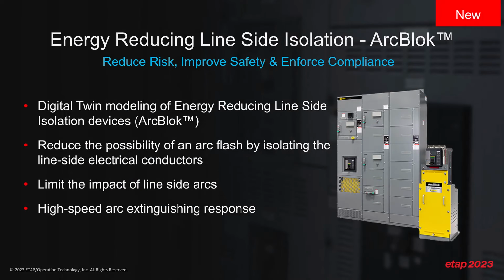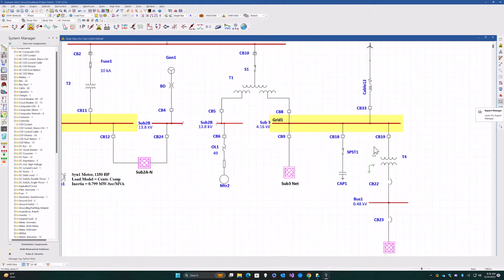So ETAP 2023 now includes the digital twin modeling of the energy reducing line side isolation device, or ArcBlok, which reduces the possibility of having an arc flash by isolating the line side electrical conductors, and therefore limits the impact of the arcs and provides high-speed arc extinguishing response. So in your arsenal of arc flash mitigation, you have one more methodology that you can use to make sure that your systems are safer, you have enforced compliance, and reduce risk for your personnel as well as the equipment. So let's just see ArcBlok in ETAP in action.